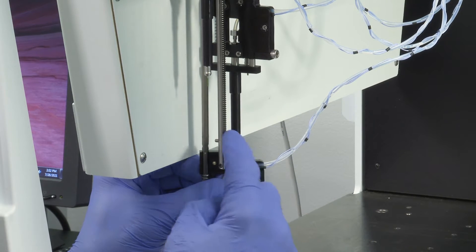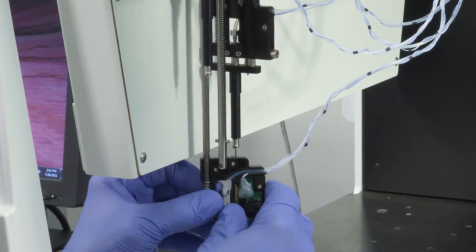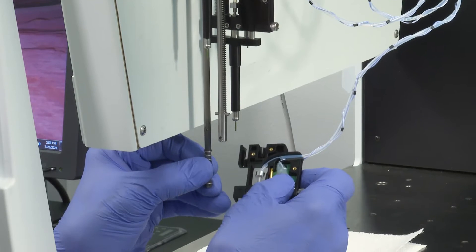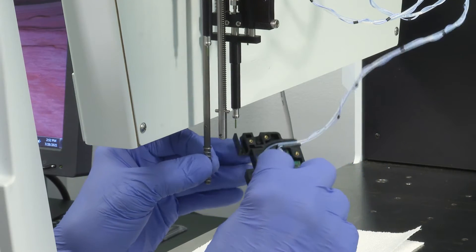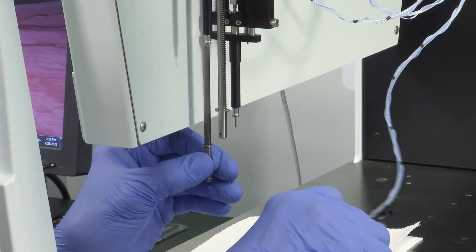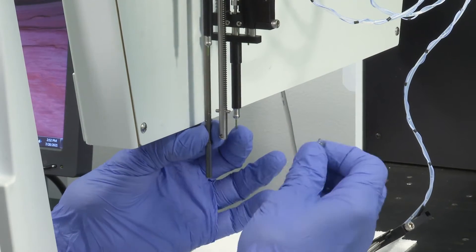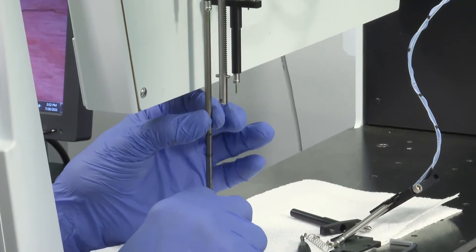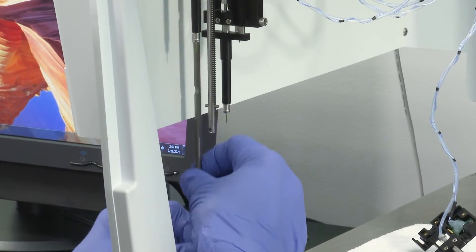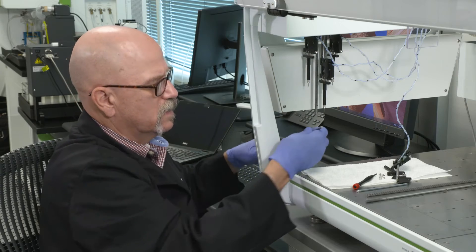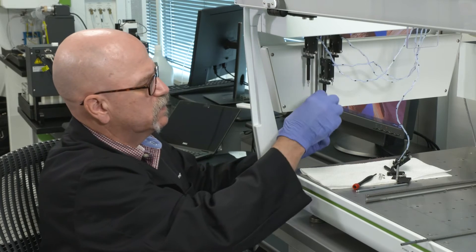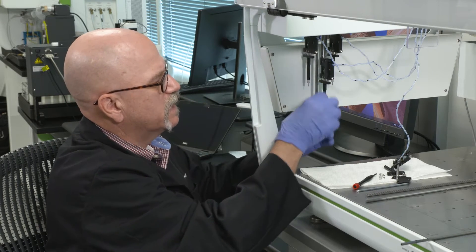You can slide the plate tip housing cover off to the side and at this point you should be able to push the tip housing off of the Z-Rack by moving it backwards. Note this one has the short end, this is tip number three. Then you're going to rock it backwards and that will release it from the guide rod. Note the VersaTip is held in place and the spring will come off the end of the guide rod. There's also a clip that we're going to reuse off of the guide rod.